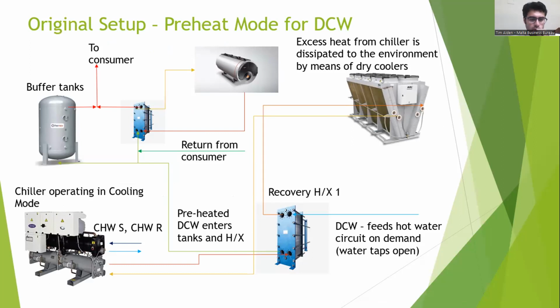Something which I have to say is that the original installation at Mater Dei already had a chiller with a heat recovery system. So what's the difference between the original system and the new implementation? The original system had a water-cooled chiller that operated as a normal chiller in chilling mode. Its purpose was to provide chilled water, but at the same time, its condenser side was connected to a heat exchanger to preheat the incoming hot water.